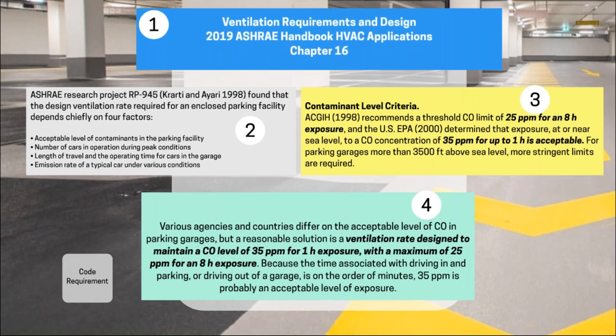The ventilation requirements are in the ASHRAE Handbook Applications Chapter 16. A research project completed in 1998 identified four key factors in determining effective ventilation requirements: the acceptable level of contaminants, the number of cars in operation during peak hours, the length of travel and operating time for cars while in the garage, and the emission rate of typical cars under various conditions - because emission rates vary from a cold start versus a warm start vehicle. Based on that, an additional study identified the design goal should be 25 parts per million for an eight-hour exposure, or 35 parts per million for up to one hour.